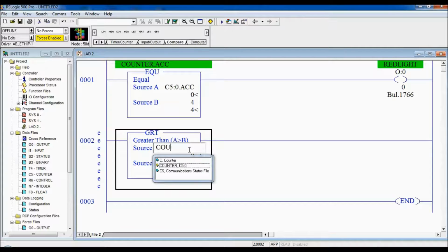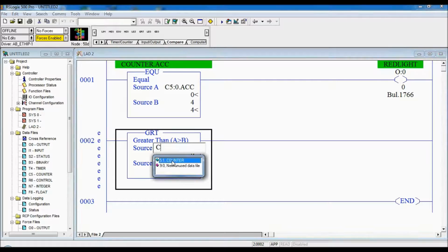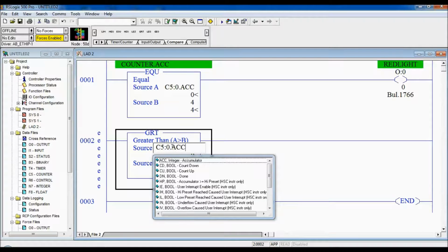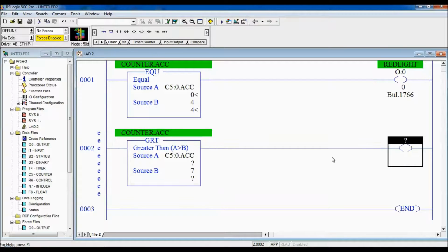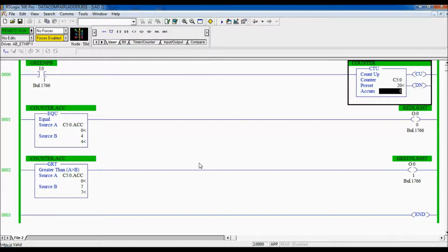We'll do greater than, and we're going to say when A is greater than B. So we'll do the counter, C5:0.ACC, the accumulated value of the counter is greater than 7. Let's turn on another light, O:0/1. All right, we're going to download that in now.